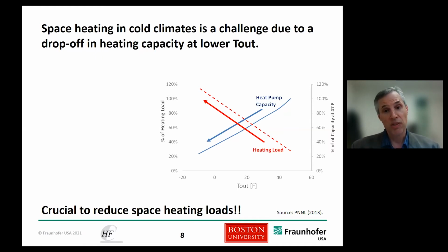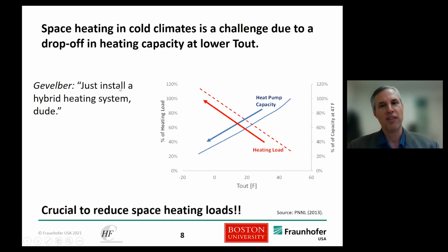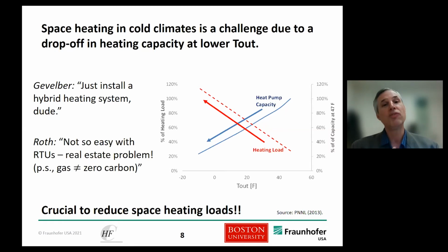A lot of times that can be electric resistance heating. And so this is a real challenge, and it really also brings out how important it is to reduce space heating loads through energy efficiency, things around enclosures, retrofits to reduce the shell loads, better windows, and then doing things with ventilation areas. Professor Gevelber's worked on a lot of those things, and they have a real impact. But one thing that comes up frequently in this discussion, which Michael and I have just talked about, is: install a hybrid heating system where you have a heat pump, which meets most of the load, and then you have supplemental heating from another kind of, usually fossil fired, system.